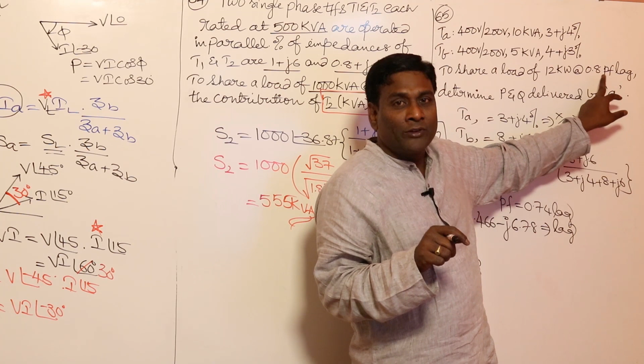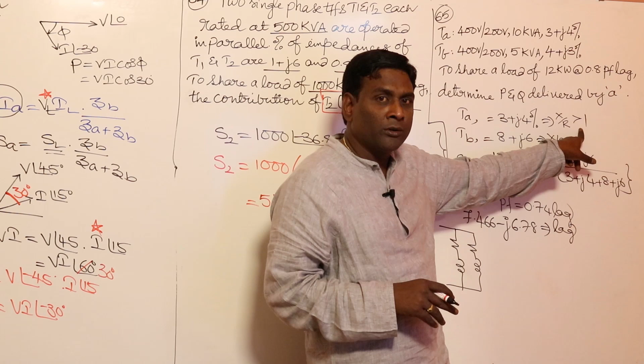So if the load power factor is 0.8 lag, trust me, I should be right. To share a load of 12 kilowatt at 0.8 power factor lag, wherever X by R ratio is more, that transformer should operate at a power factor less than this; wherever X by R ratio is less, it should operate at a better power factor than this. That's the condition we'll discuss in detail later. Between TA and TB, TA has the higher X by R ratio, so it should operate at a power factor less than 0.8 — so less power factor only. I should be right.